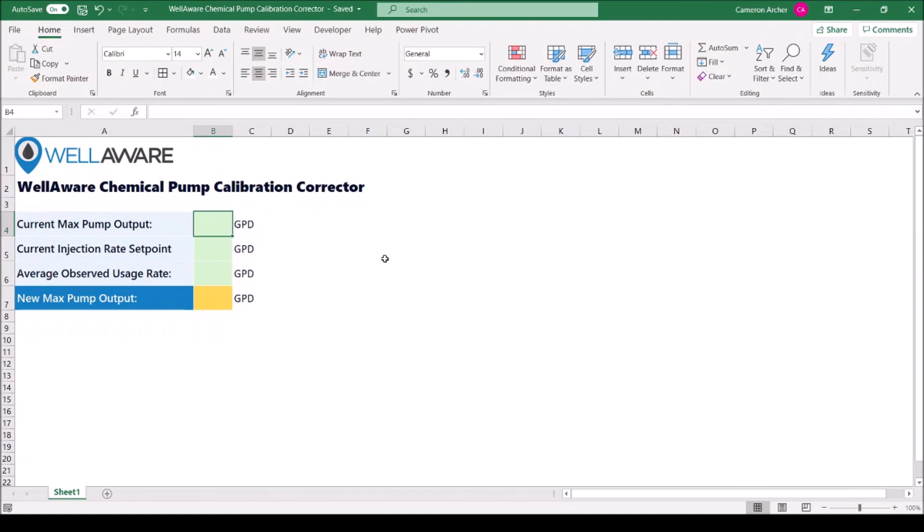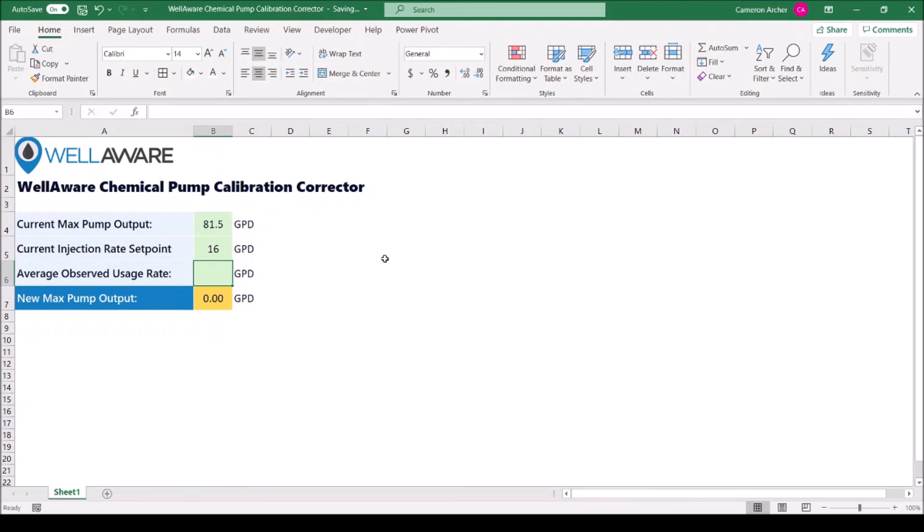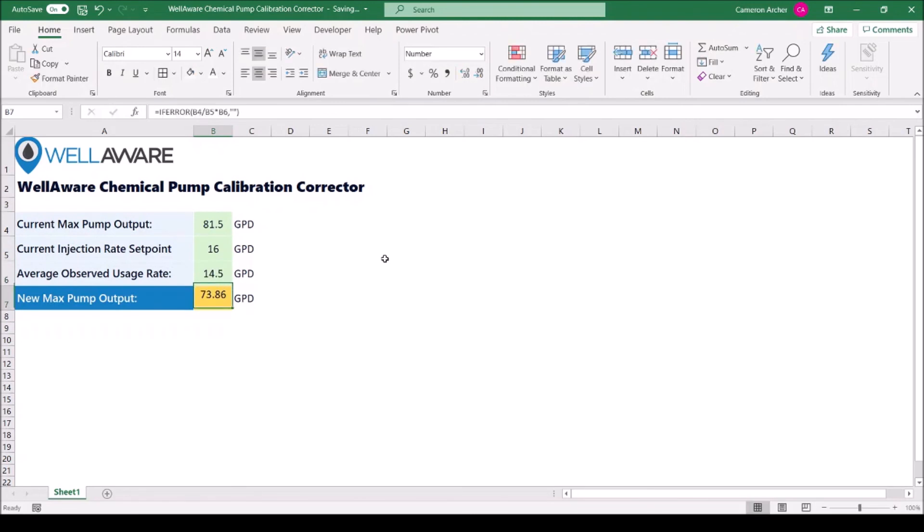So all we have to do is enter the current max pump output, which is 81.5 gallons per day, the current injection rate set point, 16 gallons per day, and the average observed usage rate, which right now is 14.5 gallons per day. And now we see our new max pump output is 73.86. We'll round it up to 73.9 gallons per day.